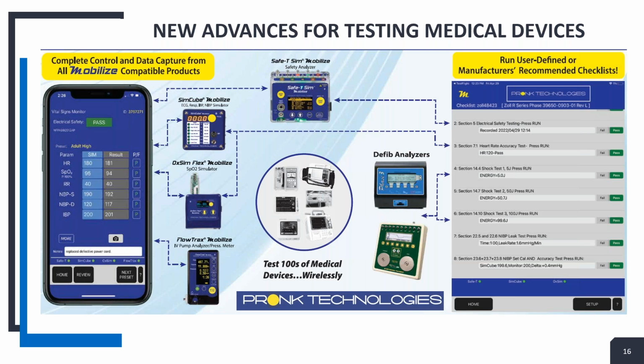So it told the defib analyzer, give me an ECG signal so I can pop one of the leads off. And we'll just take one of the hands-free leads off here and then make sure that the alarm occurs. So your guidance is there, communicating to the test equipment to go ahead and do that test. So that's the concept behind it, and then you're just pass failing and keeping going through it. So you can hit that and then done. And so that's the general idea behind it.